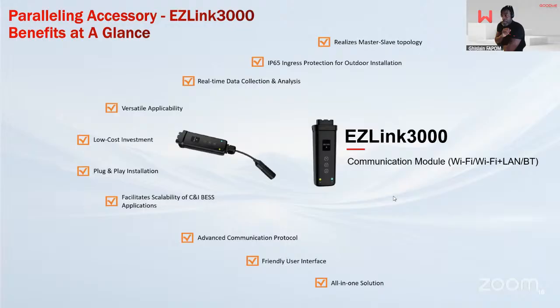This allows a master-slave configuration, with one inverter being the controller of the whole system, and the other inverters being connected through the EZLink. It's IP65. It allows real-time collection of data and analysis, and is versatile, low-cost, plug-and-play, and facilitates scalability. Of course, that's why it's there: to create a multiple effect of the system.